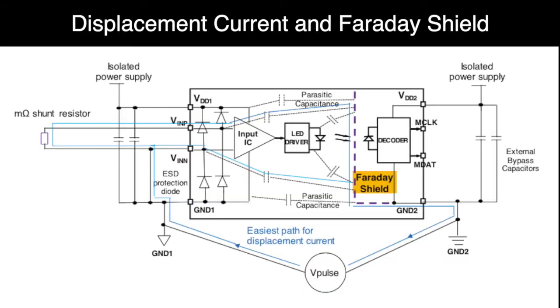The high voltage surge will induce high density displacement current from ground 1 to the input circuitry of the isolator, and then transmit over to output circuitry and ground 2 via capacitive structures or parasitic capacitance formed throughout the isolation barrier. The diagram shows the various parasitic capacitance paths formed between the wire bonds of the input circuitry or input lead frame to the Faraday shield of the Broadcom optocoupler. The Faraday shield is grounded to ground 2 and provides an electric and magnetic shielding to remove the displacement current. In capacitive or magnetic couplers, the Faraday shield is not a viable solution. A Faraday shield would block the electric or magnetic fields used for data transmission in addition to transients.